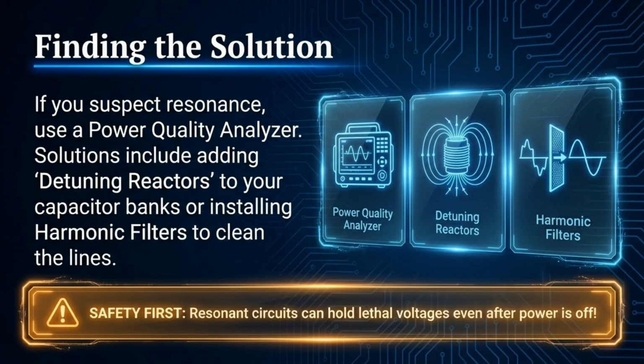If you suspect resonance, use a power quality analyzer. Solutions include adding detuning reactors to capacitor banks or installing harmonic filters to clean the lines. Remember, safety first. Resonant circuits can hold lethal voltages even after power is off.